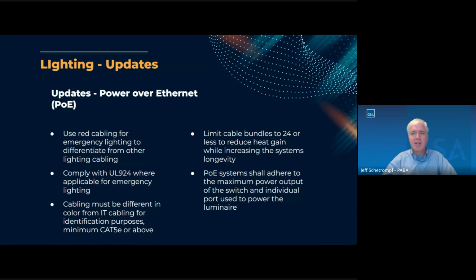The number one item that's going to degrade your PoE system over time is heat. So we specifically call out that cable bundles cannot exceed 24 cables. This is going to reduce your heat gain amongst that group of cables, and it's going to increase the system longevity.